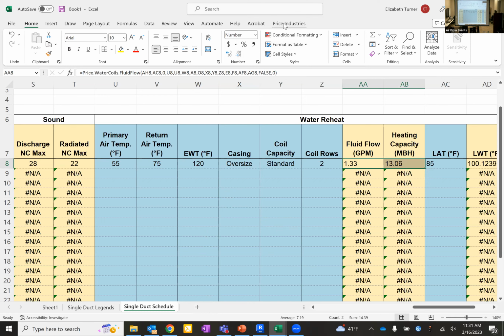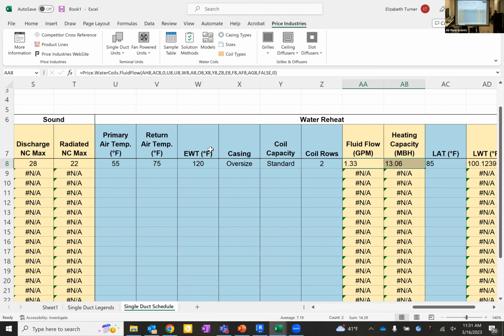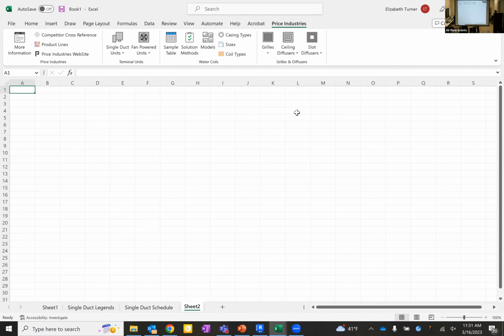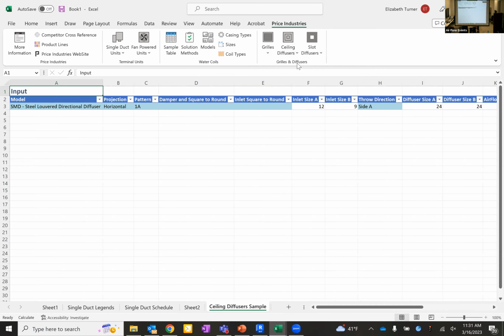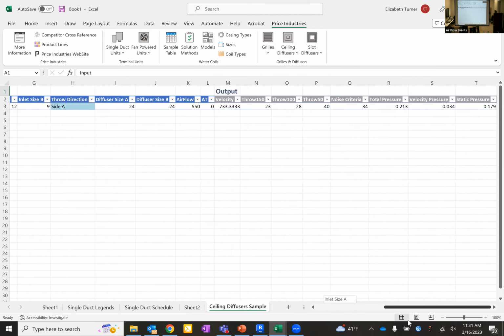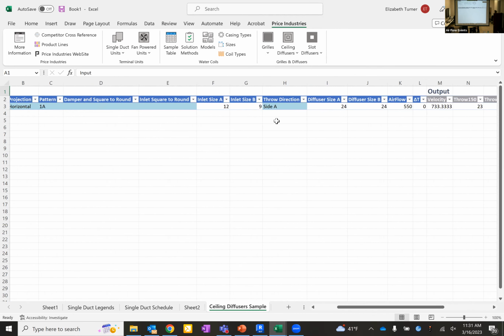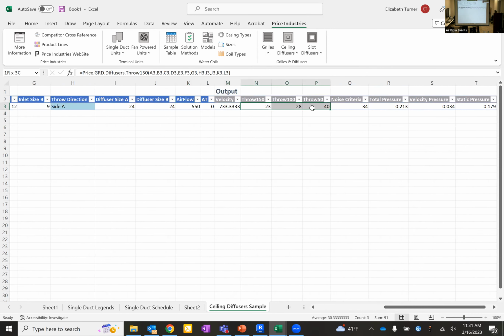So my last note here, I did point out that there's diffuser selections in here. 99% of people are not gonna be using this for actually building out diffuser schedules. What this tool is nice for is checking performance of like 1 or 2 very specific, maybe weird scenarios. It has a ton of different information, but it allows you with a single diffuser to set your sizes, set your airflow, and then see what your velocity, throw, sound level, pressure drop is, etc. We'll go over throw and all that later, but you can get all of your performance in here as well for grills.